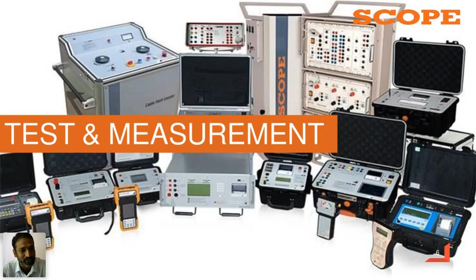These are all the testing instruments we provide for primary equipment. For circuit breakers, we have timers, contact resistance meters, and breaker analyzers. For transformers, we have turns ratio meters (TRM) and transformer resistance meters, along with other related transformer equipment. Whatever primary equipment you can name, we have the testing solution for it. These instruments fall under the T&M vertical.